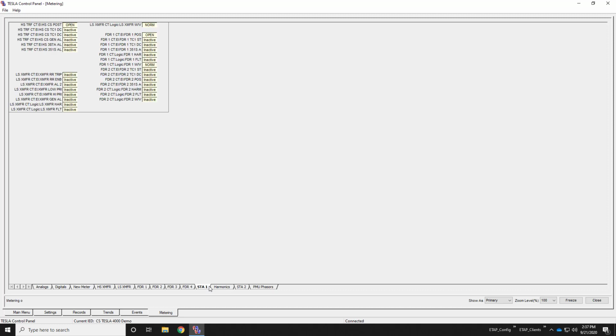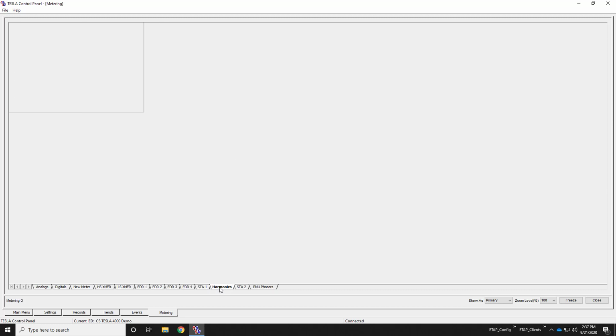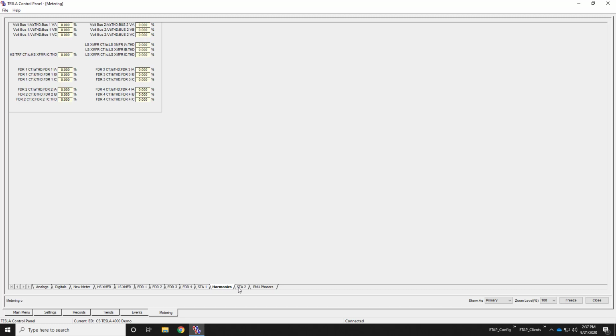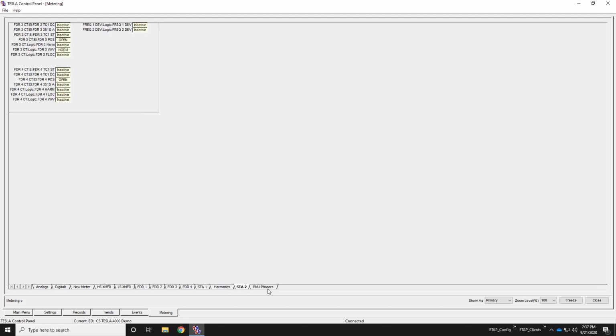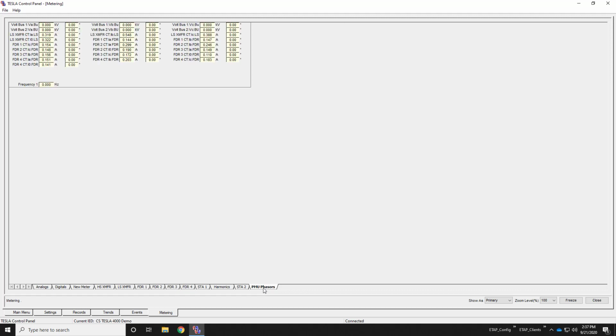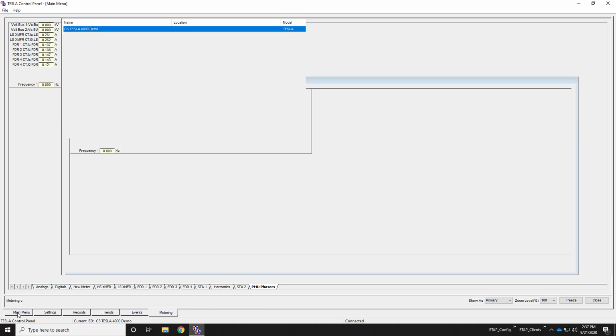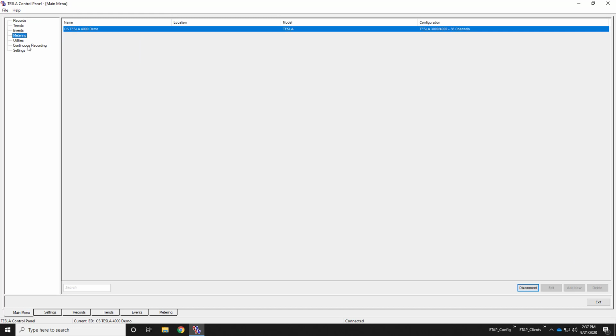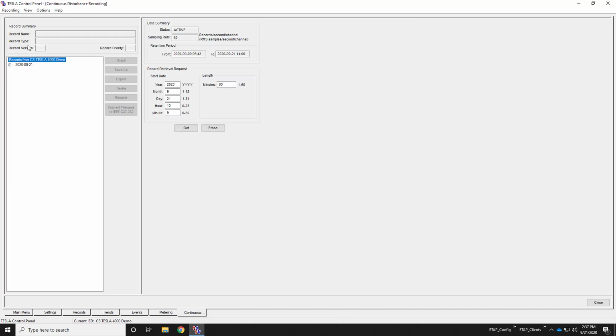So these are all of the different statuses, the calculated harmonics, not much here. And finally, the PMU phasor data. So this is that very fast phasor data available. So all of this is available within the Tesla control panel, as well as available to the SCADA system for ETAP real-time. Finally, there's the continuous recording capability, where we can continuously record and create a Comtrade file on the fly.